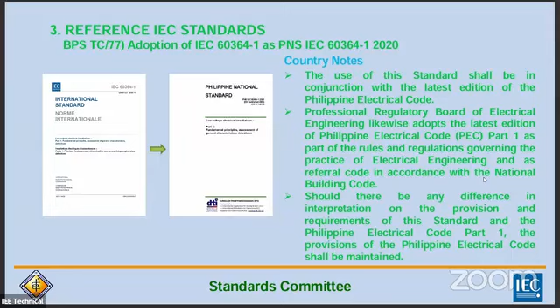Now, what is IEC 60364? It has 35 documents - 21 sections correspond to special locations, like Part 7, wherein these special sections can modify the requirements of the fundamental principles, Parts 1, 4, 5, and 6. So there are 6 main parts: fundamental principles Part 1, Part 4 is protection for safety, selection and erection of electrical equipment, Part 6 is verification and test - that's inspection, special locations, then Part 8 functional aspects. We'll discuss Part 1 since that's what we're talking about now.